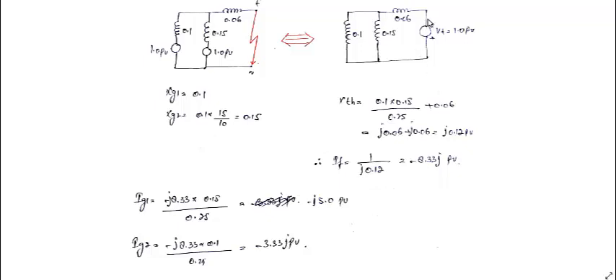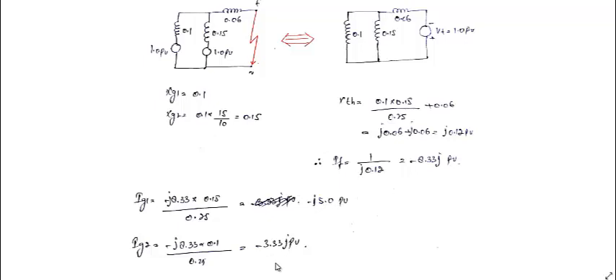Using the current divider rule: IG1 = fault current × 0.15/(0.1+0.15) = minus j8.33 × 0.15/0.25 = minus j5.0 per unit. IG2 = minus j8.33 × 0.1/0.25 = minus j3.33 per unit. You can verify: 5.0 + 3.33 = 8.33, which checks out.